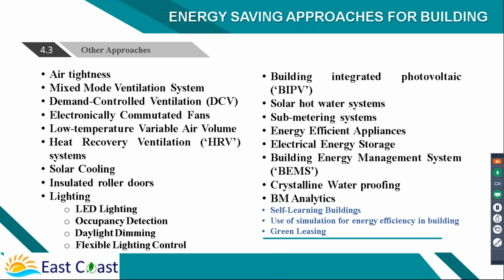Then there's solar cooling. We spoke about absorption refrigeration, the absorption machine VAM, which requires a minimum 85 to 90 degree water heat source. But solar based cooling is also available, you can produce water at 60 or 65 degrees and run what is known as adsorption, not absorption, adsorption, AD. The setup is similar to absorption, but here we use a low temperature heat source, and the chemical substance used in the system is different.